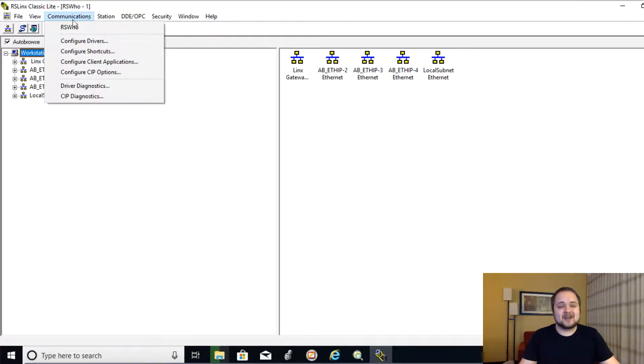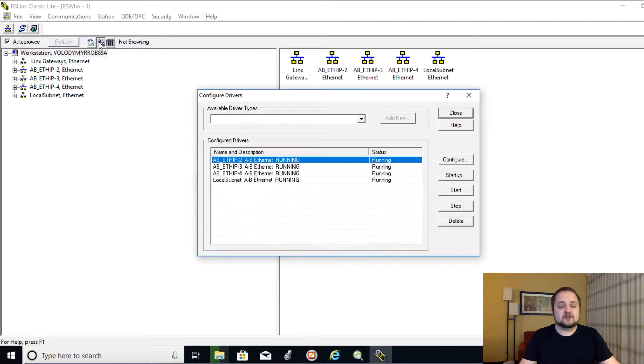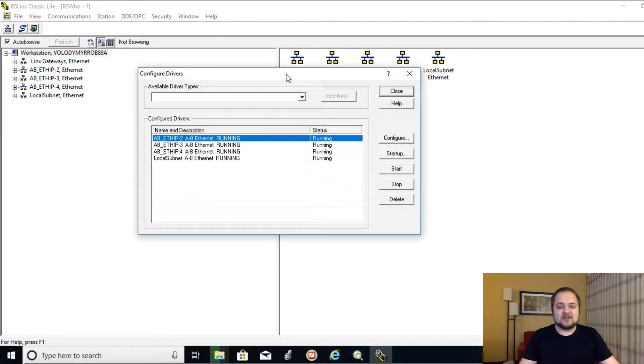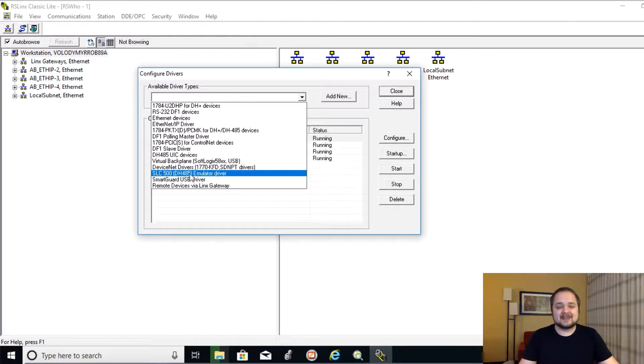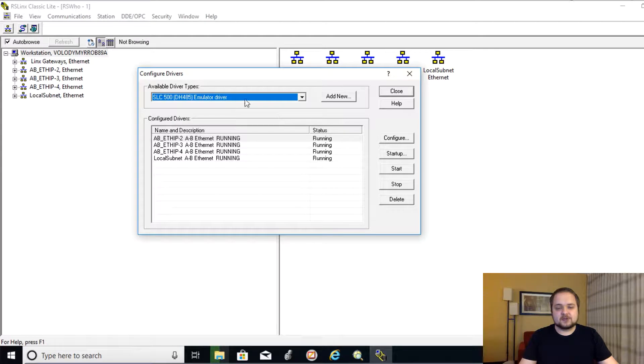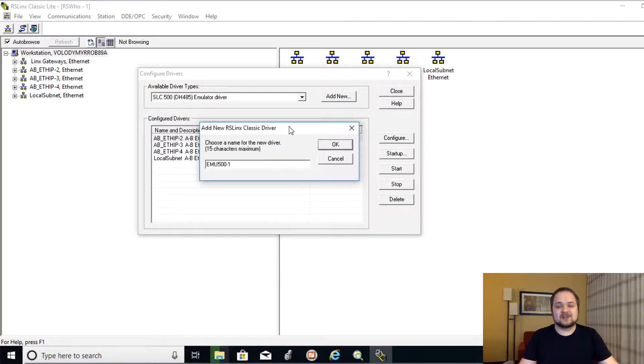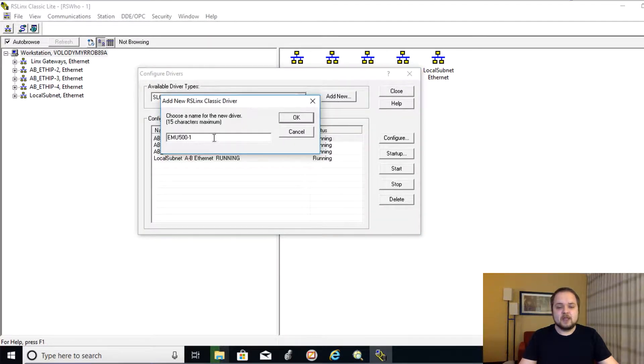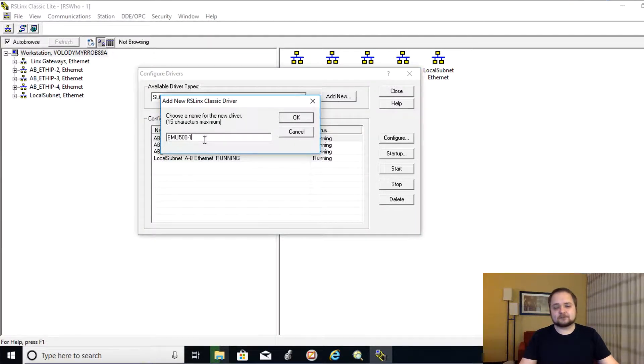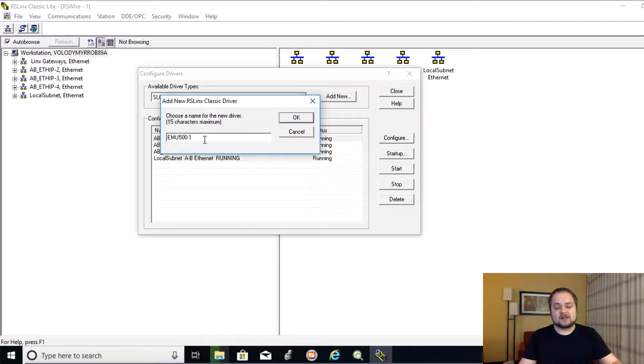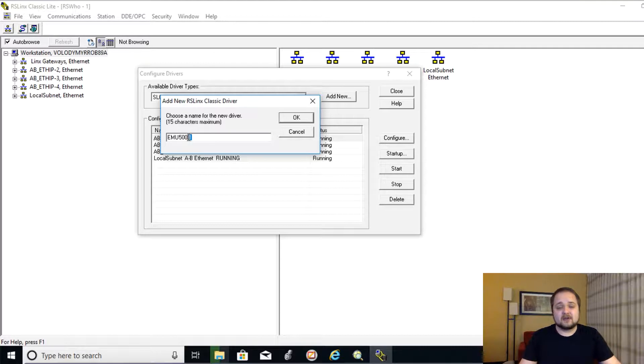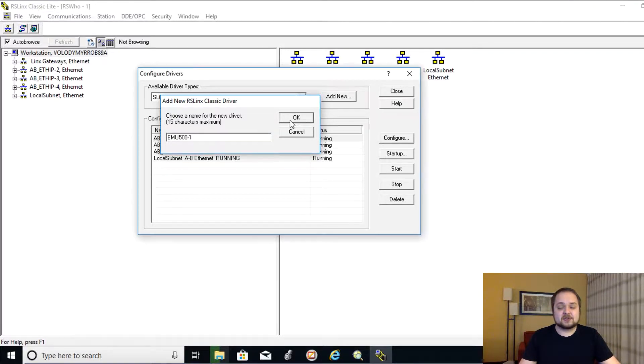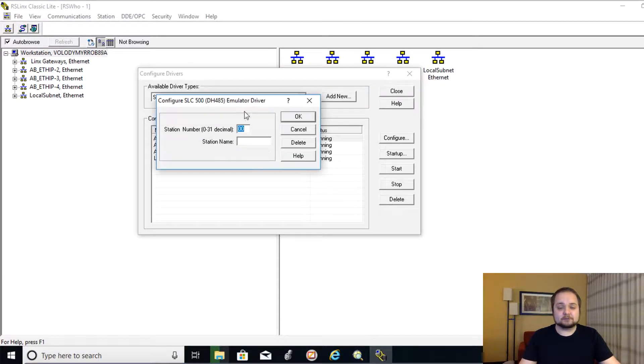You're going to click on communications and then configure drivers. From this menu, you can create many different drivers, but we're going to be interested in this SLC 500 emulator driver. So you're going to click on that and you're going to select add new. You can give it any name that you desire just for it to be more recognizable. But since you're going to have only one instance, most likely of this driver, I would just leave it as such. You can hit OK.